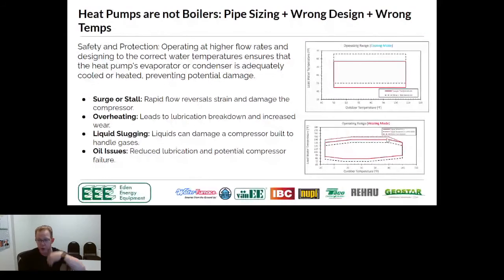And at that point, you're going to overheat the compressor. You're going to start cooking lubricants. You're going to break them down. And the reality is it's really bad wear and tear on the equipment. So we want to make sure that we always have the right flow, the right size pipe, and that we're not trying to achieve water temperatures that we shouldn't.